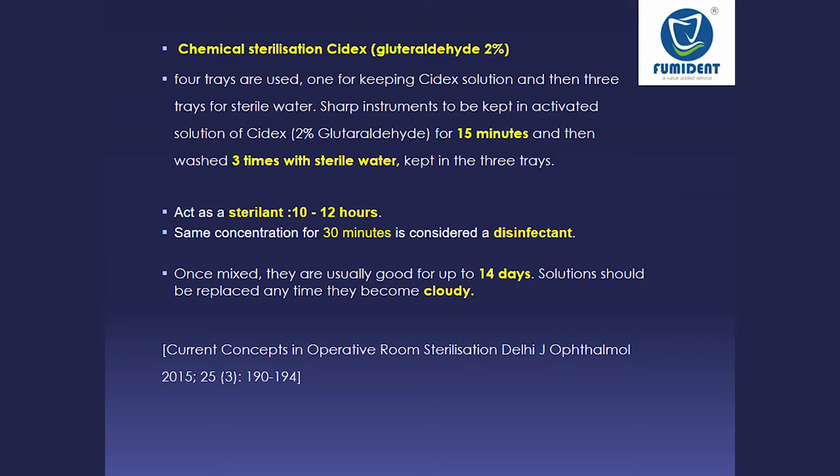Again, once you prepare this solution, you have to make sure of the concentration recommended by the manufacturer, because I have seen in many places Cidex solution get diluted, but that dilution was not proper. Once you prepare this solution, you can keep it for 14 days at most, or if you observe any cloudiness inside it, you have to discard the solution.